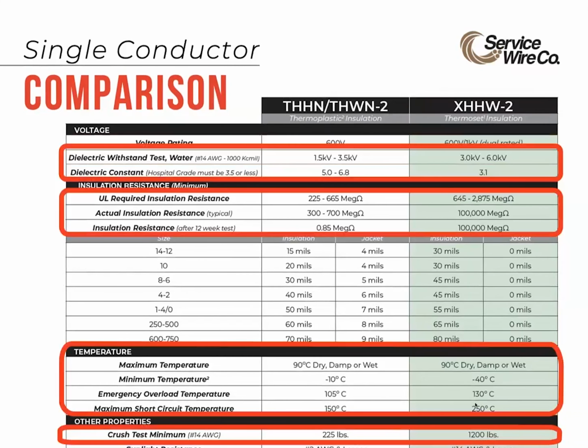In this comparison chart, you can see that Service Wire's Thermoset XHHW-2 has a dielectric constant of less than 3.5, meaning the cable's insulation has a greater ability to release leakage current. And the cable insulation resistance is substantially higher than PVC. This means the cable can handle more spikes and inrushes over longer periods of time while protecting critical circuits at risk of electrical interference from high leakage currents. XHHW-2 also has a higher maximum and lower minimum temperature rating, protecting the cable in open air installations.